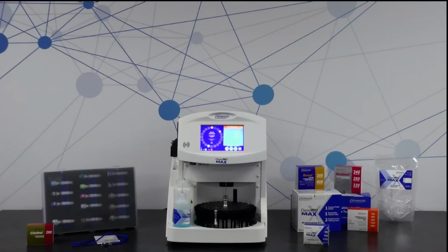Does the freezing chamber and impactor ever need extra cleaning like the old osmometers? What's interesting about the OsmoPRO MAX is that even though it leverages freezing point depression technology to freeze the sample and take the freezing point plateau measurement, it does not use an impactor. I don't know if you could hear because I'm talking through my microphone here, but when you run each test, let's see where we're at with the current test. Or did we run everything already? Nope, we're still on the current test.